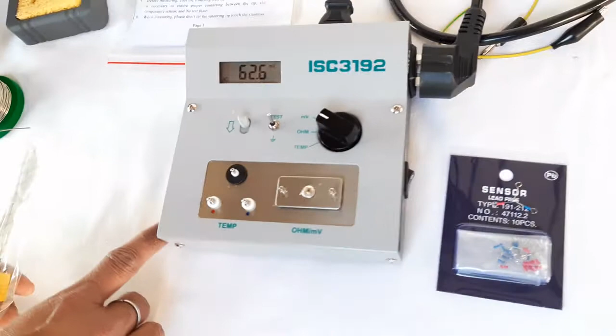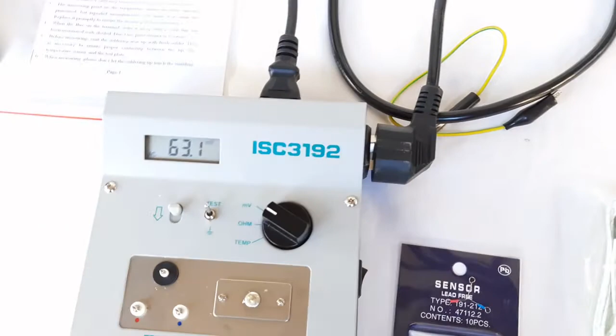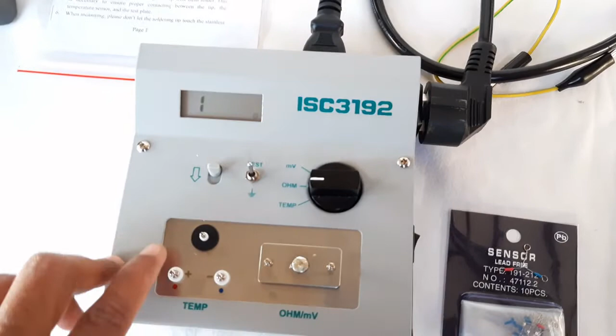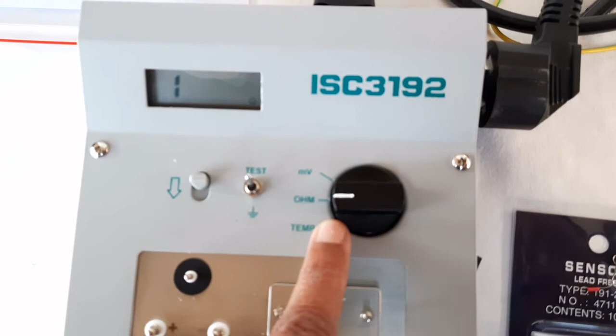See, this is the cord which we have connected to the soldering station, is connected to this calibrator through this port, and the power supply to this soldering station is supplied through this calibrator. So this is the on off switch. We will switch it on first. This thermocouple can also be connected to this port, getting the polarity right. So there are three functions. We can use this calibrator for three different functions. First one is for setting the leakage voltage. Second one is for checking the leakage resistance, and third one for measuring the tip temperature.